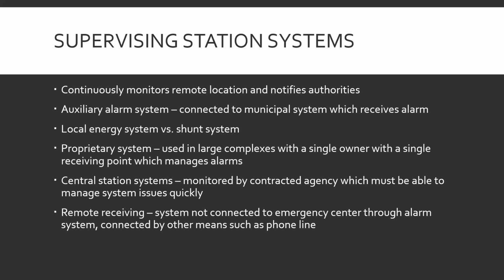Local energy system versus shunt system. Local energy alarms are able to sound even if the tie-in to the municipal system goes out. There's a big storm, and for whatever reason there's an interruption in the circuit or wiring to the dispatch center somewhere. The local energy system will still alarm. There's a catch, because the signal isn't getting out of the building to dispatch. The alarm will only sound at the building, which makes it like the earlier example where the alarm's going off, someone calls dispatch, and they go, all right, we'll send the fire department.